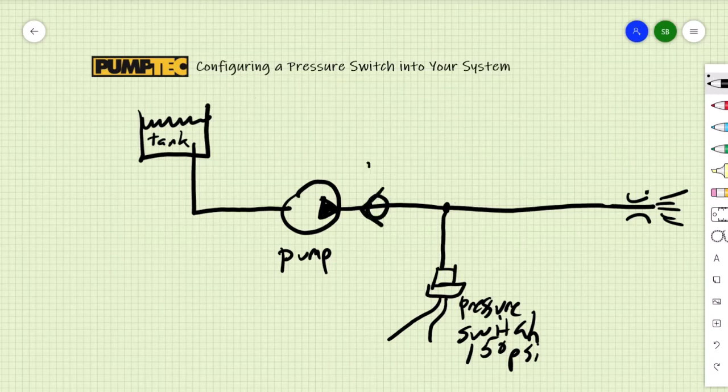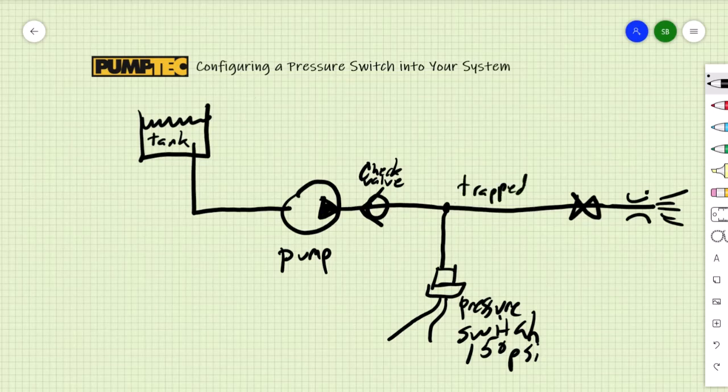The pressure switch will sense the trapped pressure between the pump and the nozzle. You need to trap the pressure with a check valve and a spray gun. This trapped pressure will only stay trapped if your check valve is a positive seal and also your spray gun doesn't leak past.